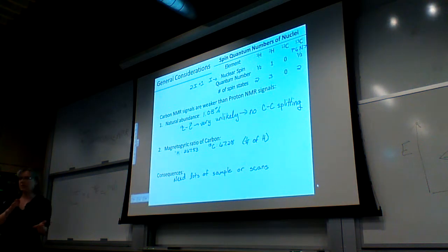The instrument itself is going to change its radio frequency. So it's looking at 100 megahertz rather than 400. Okay, because it knows it's a weaker signal. Well, the 100 relates to the magnetic gyromagnetic ratio, so you have to be able to correlate those. And you do it differently for each atom, or element, I should say.